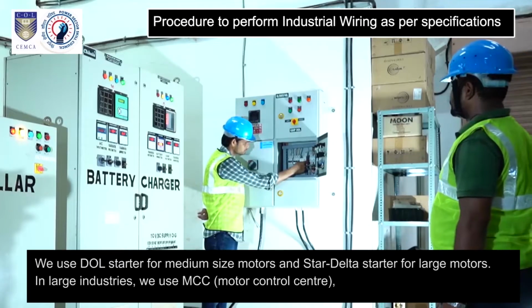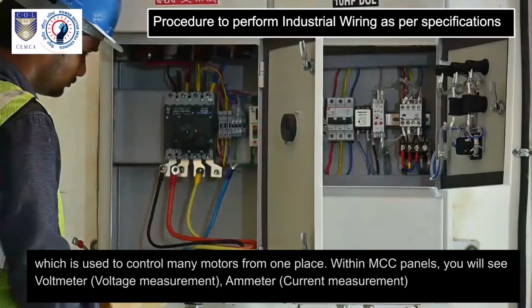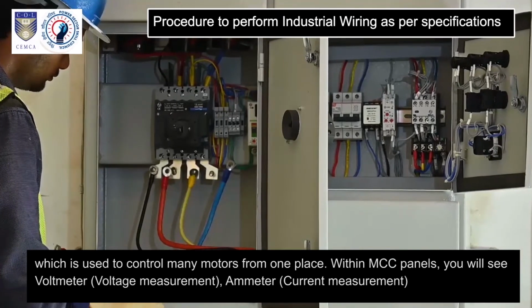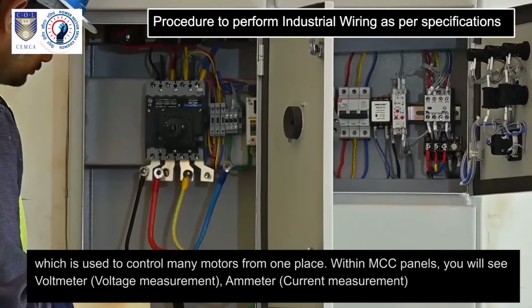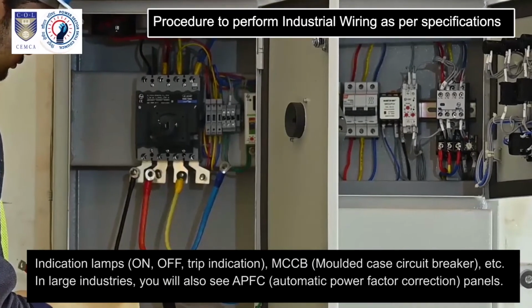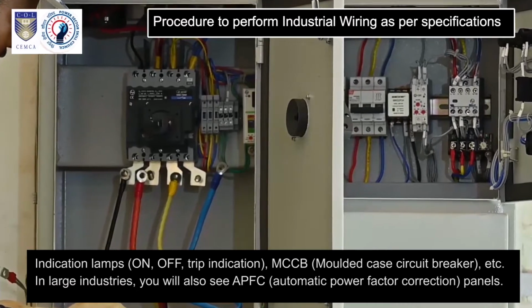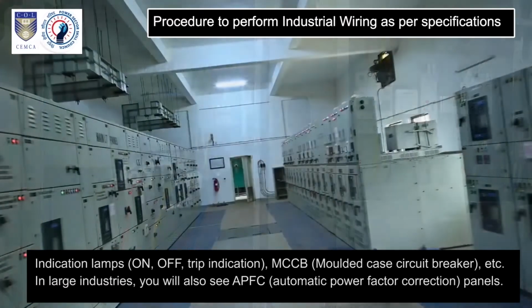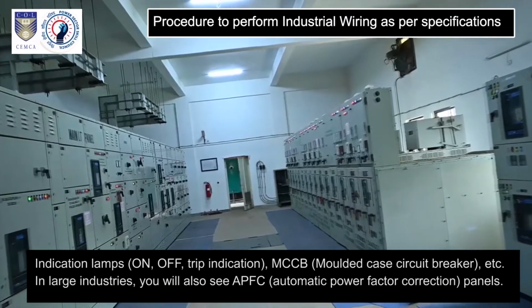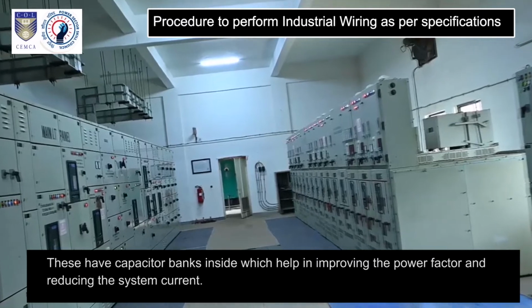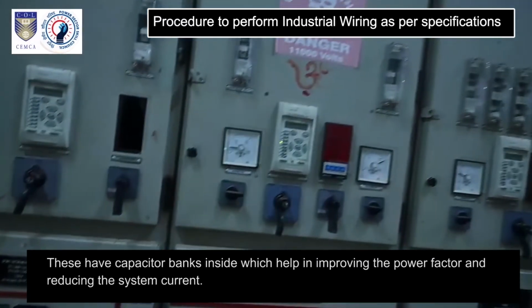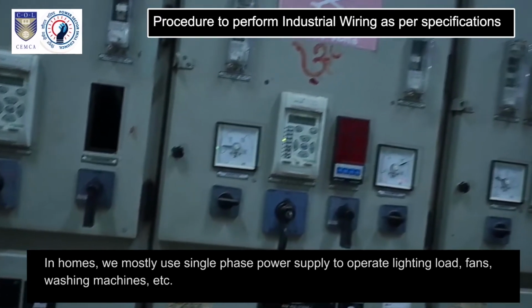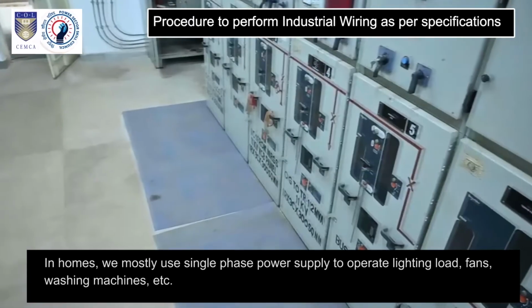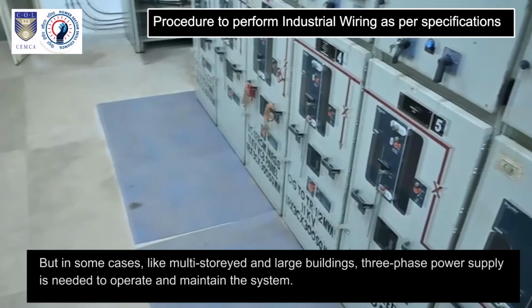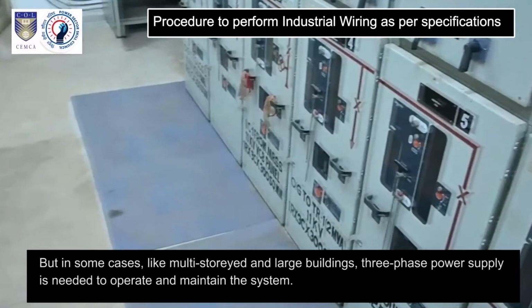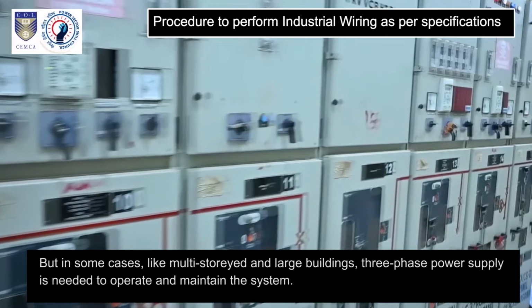In large industries, we use MCC, Motor Control Center, which is used to control many motors from one place. Within MCC panels, you will see voltmeter for voltage measurement, ammeter for current measurement, indication lamps for on-off, trip indication, MCCB molded case circuit breaker, etc. In large industries, you will also see APFC automatic power factor correction panels. These have capacitor banks inside, which help in improving the power factor and reducing the system current. In homes, we mostly use single-phase power supply to operate lighting load, fans, washing machines, etc. But in some cases, like multi-storied and large buildings, three-phase power supply is needed to operate and maintain the system.